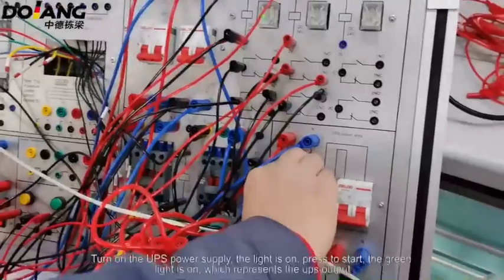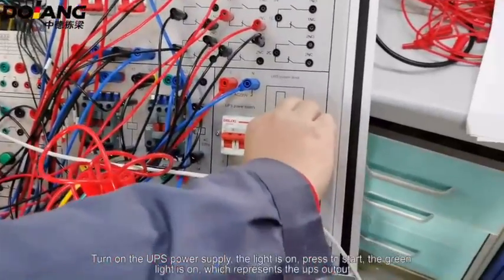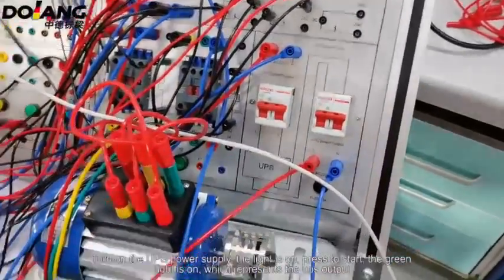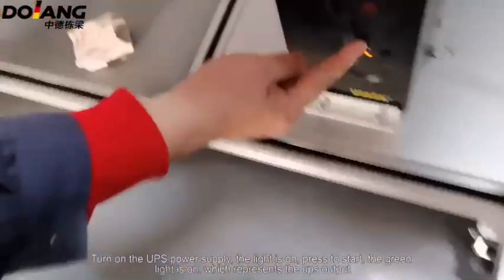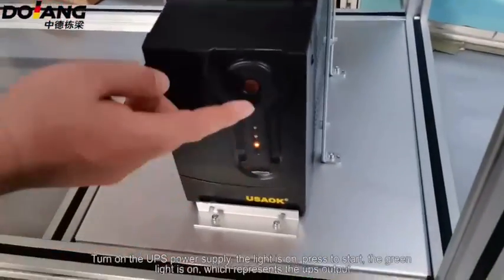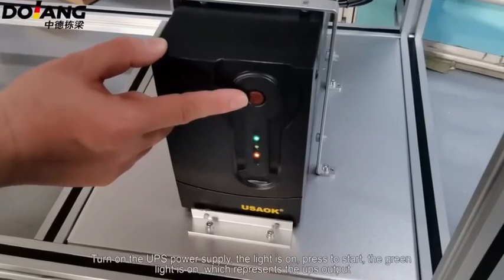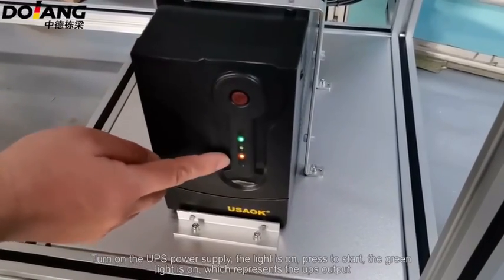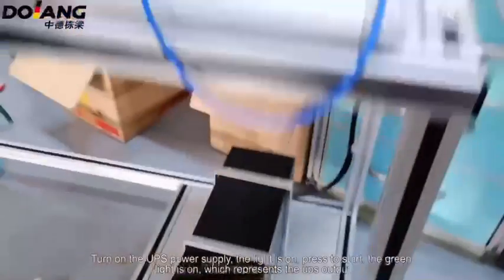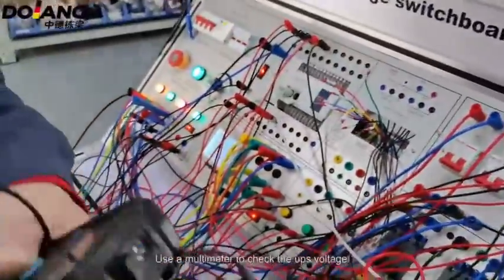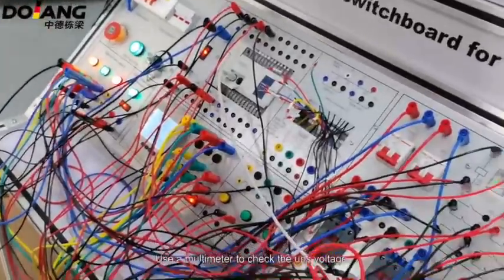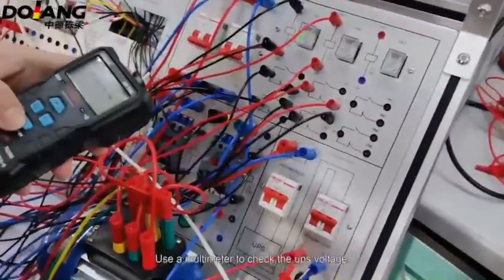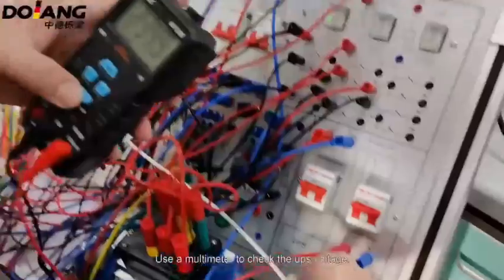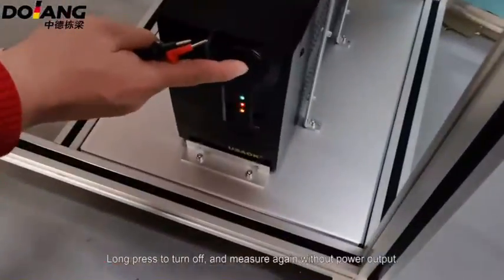Turn on the UPS power supply. The light is on at this time. It means the UPS is charging. Press start and the green light is on, which means the UPS is outputting. You can measure the output voltage of the UPS power supply, 235 volts. Press the off button to turn off, and there is almost no voltage in the measurement.